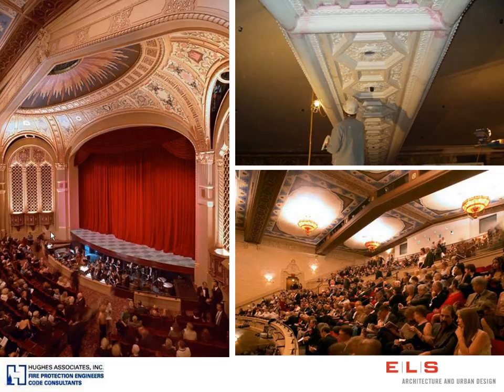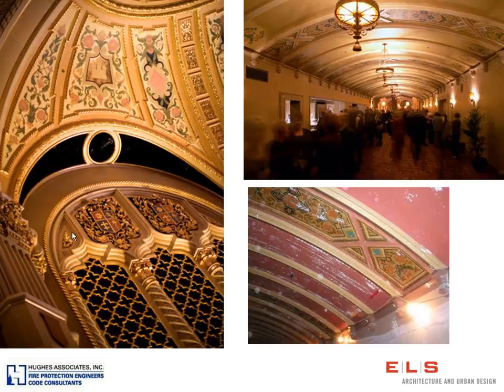In the area in front of the proscenium, the first approximately 30 feet or so from the curtain line, the painting was in very good shape and much more decorative. And even though we wanted to install sprinklers, which was part of our program, we ended up working within the vocabulary of that architecture, that decorative painting. So here was obviously the stencil work. Here was what we would call the plain painting. So obviously we work within those areas to install sprinklers such as this, and still obviously meeting all the criteria. But the important thing to look at here is that this is all very well planned out in the sprinkler bidding drawings. This is the type of thing that you really cannot leave to the design build industry.